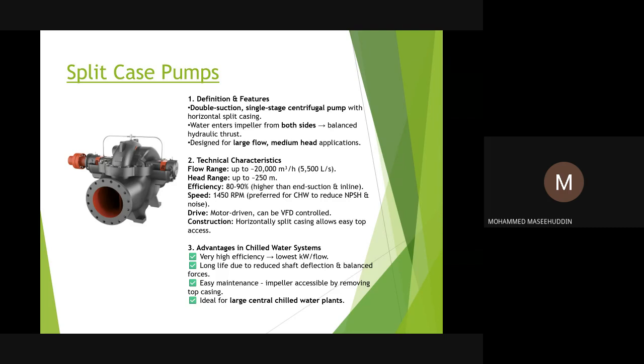These types of pumps have larger flow rates with higher heads. They can take care of up to 20,000 cubic meters per hour of flow rate, and heads up to 250 meters. These pumps are typically used in district cooling plants, where we need about 250 or 300 kilowatt motors. These pumps are capable of handling those kinds of heads and flows, and that kind of system pressure, because the system pressure in a district cooling plant will be much higher than in any of the buildings. So this is capable of handling those pressures, flow rates, and even the dynamic heads.